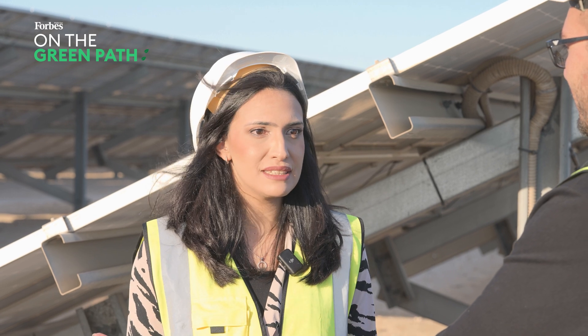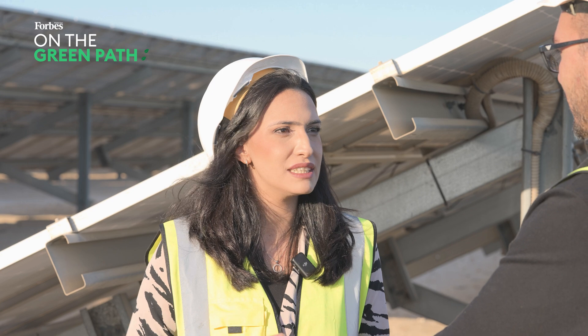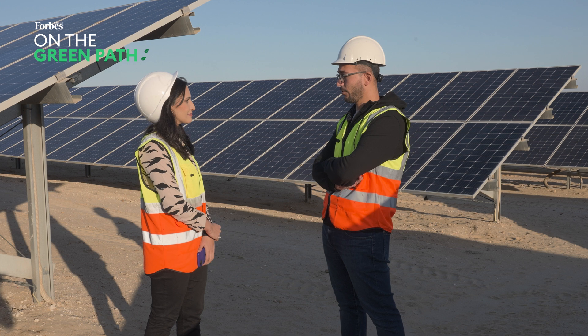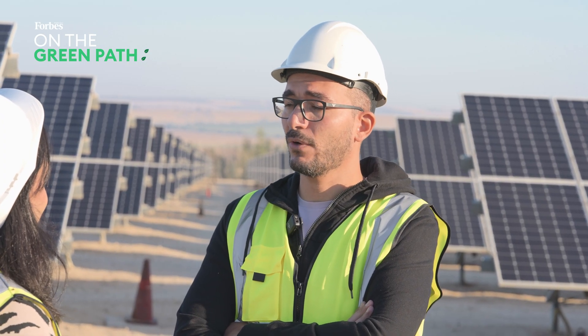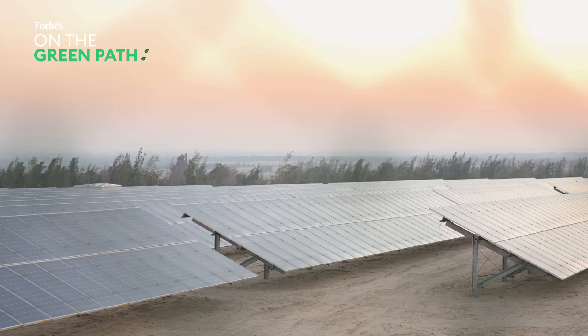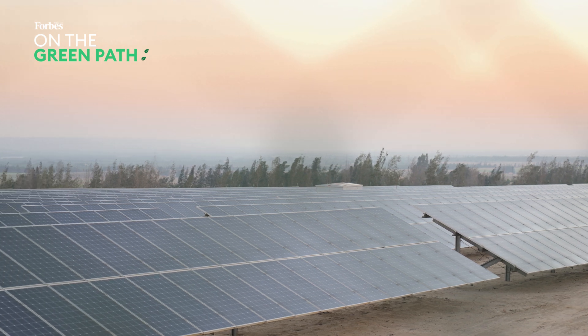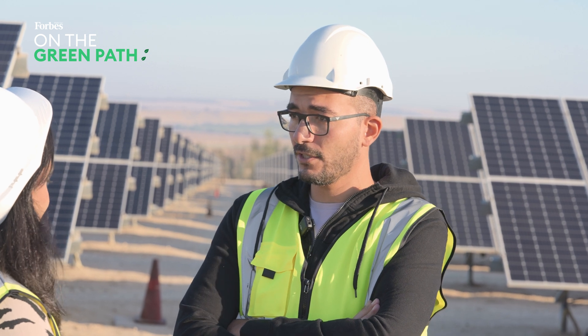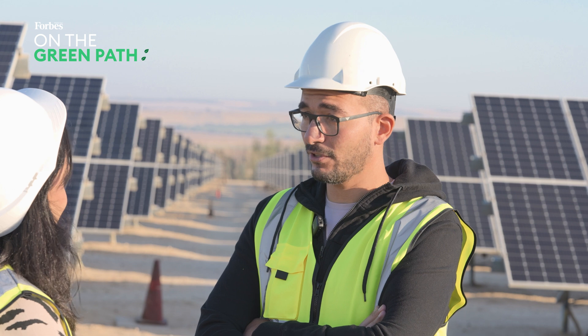This is all very impressive — the infrastructure is massive — but this will not last forever. Solar panels typically have a life cycle of around 30 years. What happens after that? The solar station would actually still work after 30 years, but at that point it probably wouldn't be efficient. So it will be one of two things: either removal of the solar station and recycling of the materials, or rehabilitation of the station — changing the panels, changing the inverters, changing the main components — in order to have another 30 years of extra electricity supply.